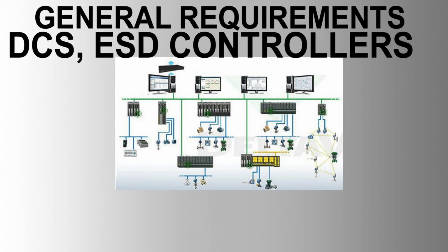Signals exchanged between ESD and MCC are interfaced through interposing relays located in the substation. Signal from IPCS to ESD used for any executive action shall be hardwired, and serial communication is not acceptable for this purpose.